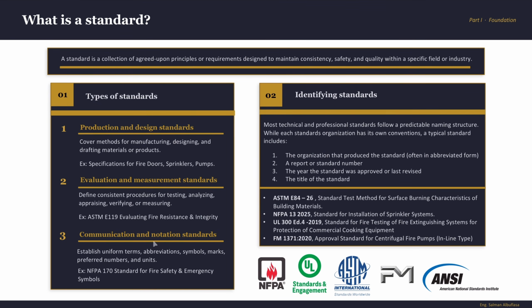Finally, the communication and notation standards. These set the uniform common language: the terms, the abbreviations, the symbols, the units. Take NFPA 170 as an example. This is exactly why fire exit signs look the same everywhere. And there's also NFPA 704, the hazard diamond that you usually see on chemical stores, chemical storage tanks, and laboratories. The four colored quadrants with numbers from 0 to 4: red, blue, yellow, white. No words needed. So let's say a firefighter who's trained on NFPA 1001 and 470 approaches that building, he can read that diamond from far away. No words needed. He'll recognize that. That's uniform common language.